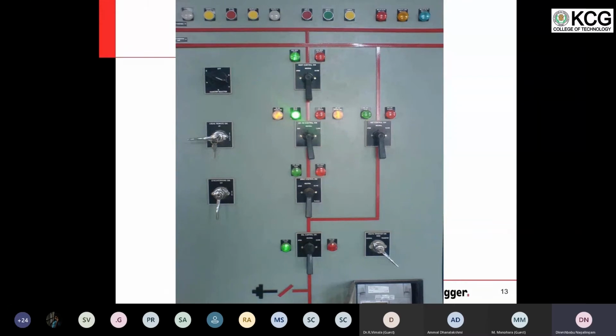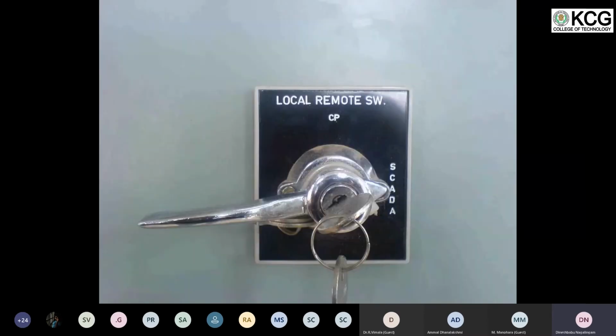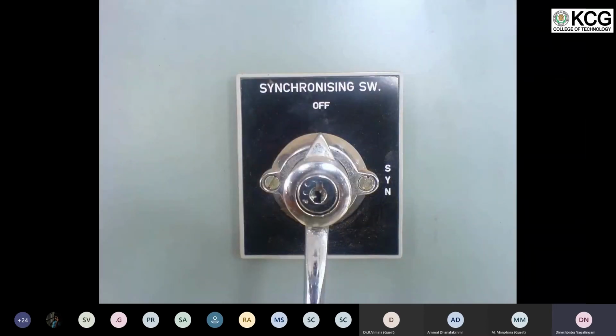Now, synchronization is required only for the 4th condition, when both sides are live. If one side is dead or both sides are dead, there is no need to synchronize. Or even if you try to synchronize, it will not permit us to synchronize because the other end is not having voltage, frequency and phase angle. Therefore, only during live bus and live line condition, we will use synchronization. In other situations, we would keep it in off position.